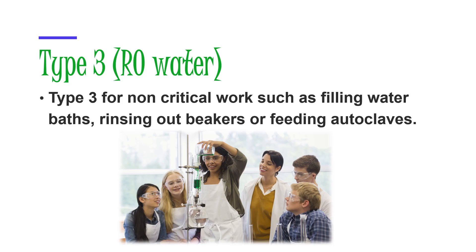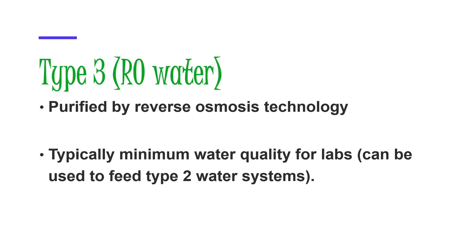Type 3 water is referred to as RO water, which stands for reverse osmosis water. It's used for non-critical work such as filling water baths, rinsing out beakers, or feeding autoclaves. These are achieved through reverse osmosis technology and represent your minimum water quality for labs. They are further purified to provide Type 2, and Type 2 is further purified to provide Type 1 water for high-sensitivity assays.